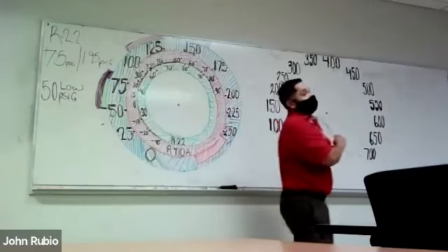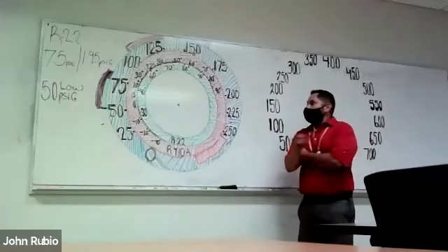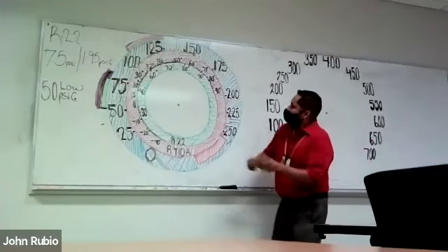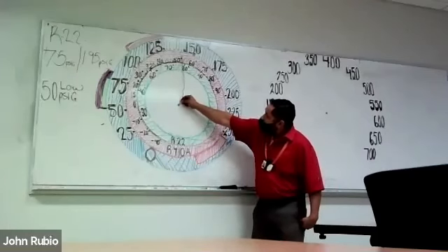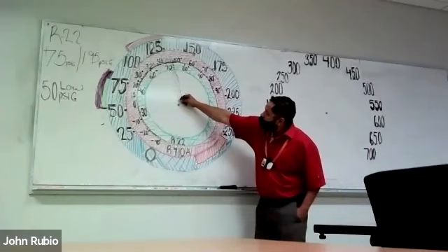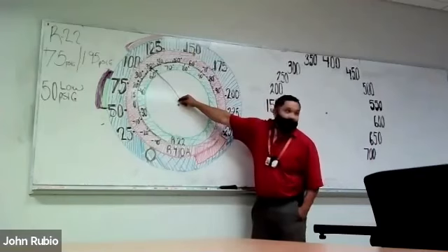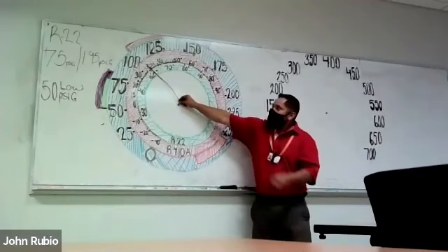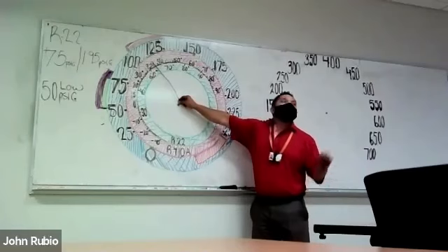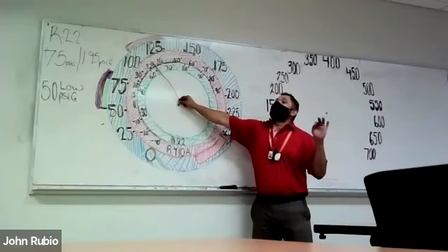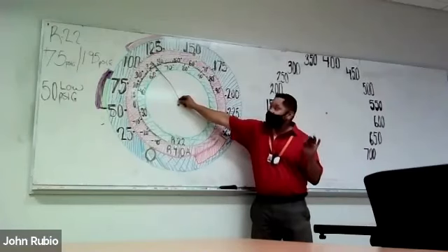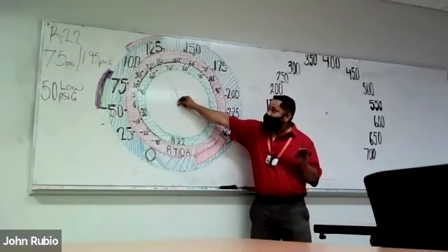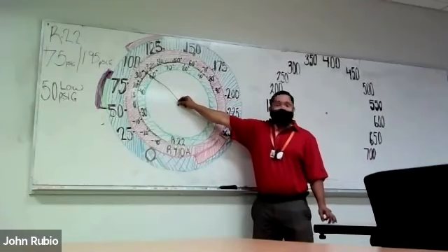Lower tier companies don't think like that. So let's watch what happens when we finally use our bars to find pressure. We see now 32 degrees at 100 PSIG. It's not a mystery. This is why we can anticipate and predict that if we leave a 410A machine sitting below 100 PSIG, sitting below 32 degrees, it might freeze up.